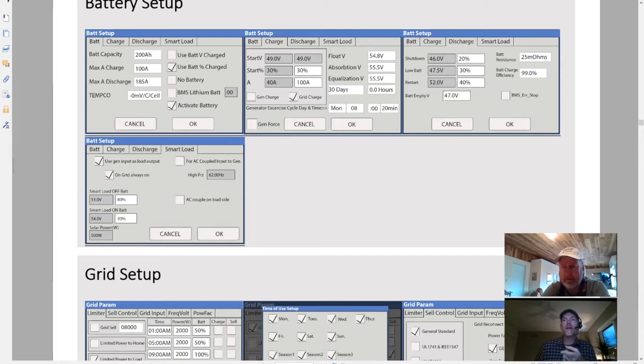Okay, so the thing that happened with you and Nate is essentially this number here, the float or absorption voltage. That number was too close to the max of what the BMS was at. So the BMS was saying, hey, you told me to open contactors at such and such voltage. I'm going to open contactors because you're getting really close.